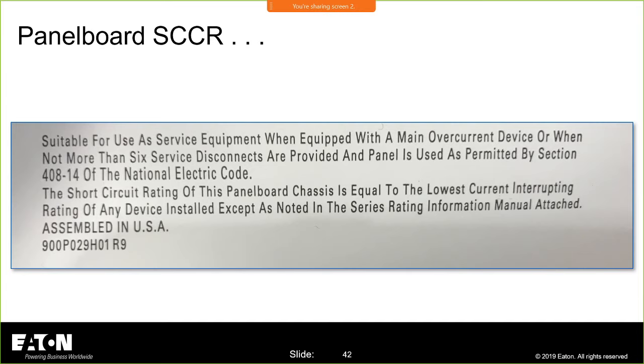So the rating of this equipment is really determined in the field, by what you're installing in that equipment. That's an important thing to remember, and I don't think we think about that when we go to the supply house and start ordering overcurrent devices. And a lot of your electrical inspectors are going to be looking at all the interrupting ratings. Now that we're going to have an available fault current marked on the outside, you're going to have to make sure that all of the interrupting ratings are greater than that available fault current, and that will establish the short circuit current rating of that equipment.